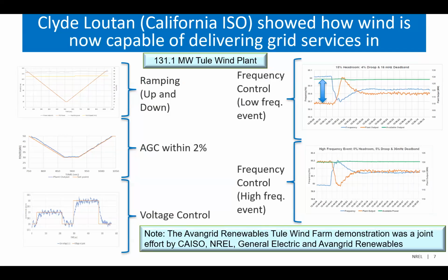One issue is that to deliver these attributes, the wind plant has to operate with some headroom — backing off from available power to a lower level in order to deliver grid attributes. The question comes up of who pays for that lost revenue. How do you compensate a plant that was designed and financed to deliver all available power at all times, now running in a different mode?